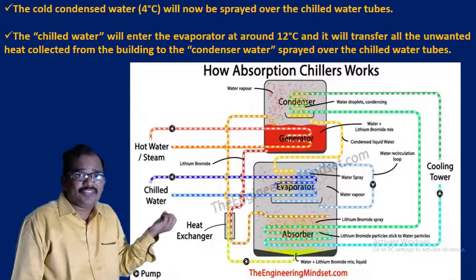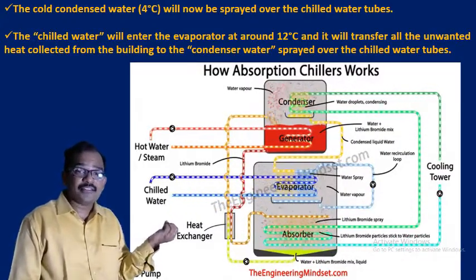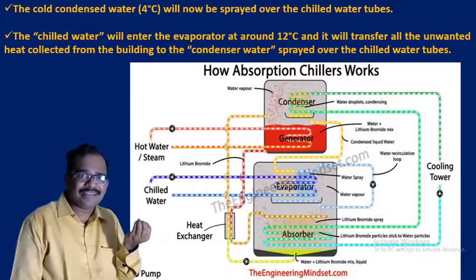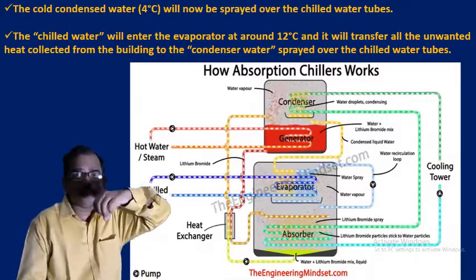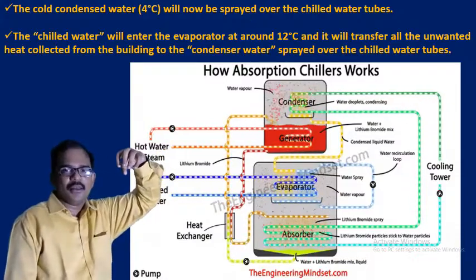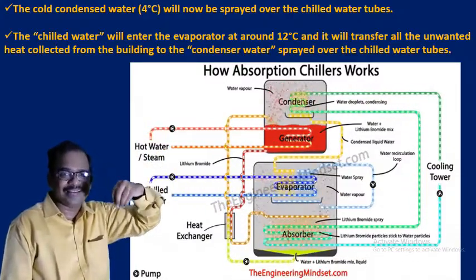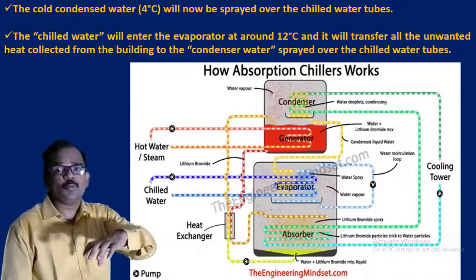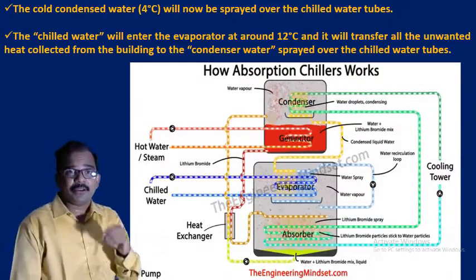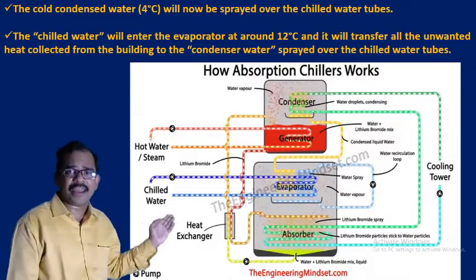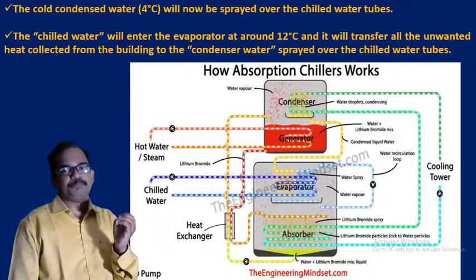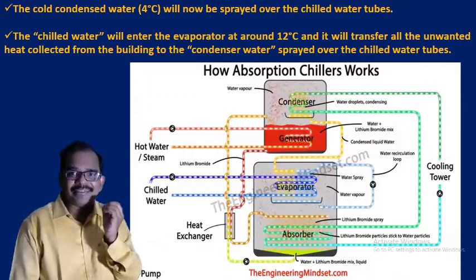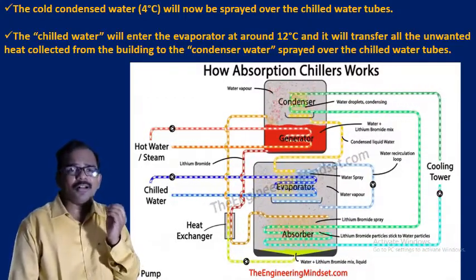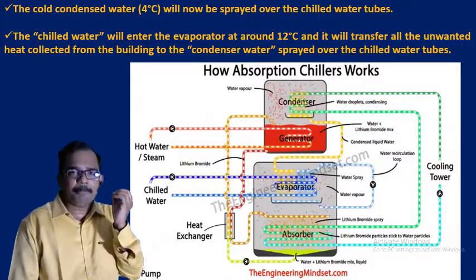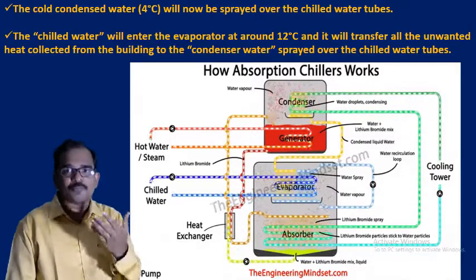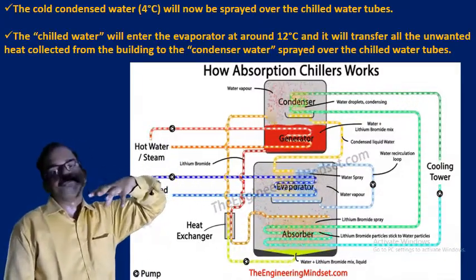So the cold condensed water, that is the water coming from the condenser which is at 4 degrees centigrade, will now be sprayed over the chilled water tube. Now the condensed water which is at 4 degrees centigrade will be sprayed onto the chilled water tubes. Why? Because the chilled water will enter the evaporator at around 12 degrees centigrade, and it will transfer all the unwanted heat collected from the building to the condenser water sprayed over the chilled water tube.